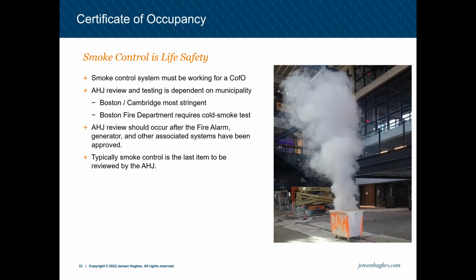Smoke control special inspection: after that's being done, usually the AHJ will review the smoke control once the fire alarm, generator, and other associated systems have been approved. So before you submit the smoke control special inspection report, make sure that the fire alarm inspection has been signed off on, and then you give 1 to 2 weeks. In Boston, it's more like 2 weeks from when you submit the report to when the AHJ will come out to do the review of a smoke control system.